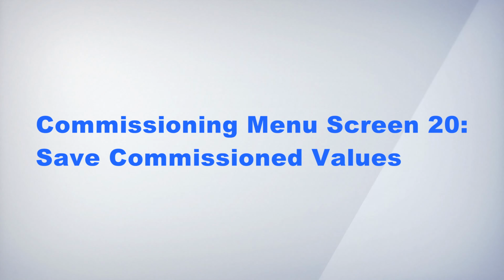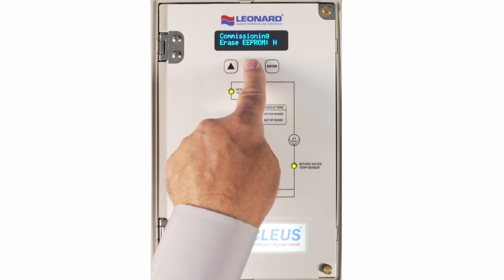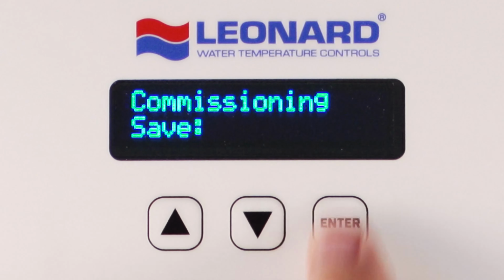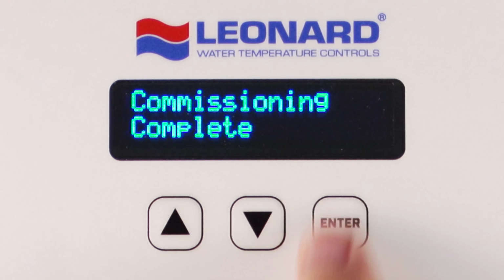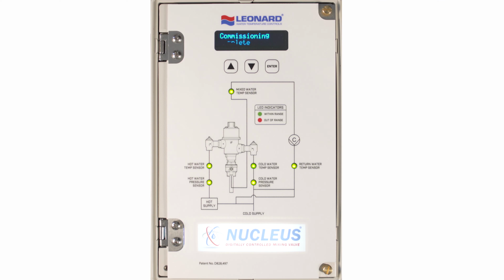Commissioning menu screen 20. Save commissioned values. Pressing down 19 times displays Commissioning Save, No or Yes. If selecting Y, this feature will save all commissioning menu settings if they have been altered. Selecting N will not save any altered values and will not commission the controller if it has not been commissioned. Selecting N will also exit commissioning mode, and the home screen will then be displayed.